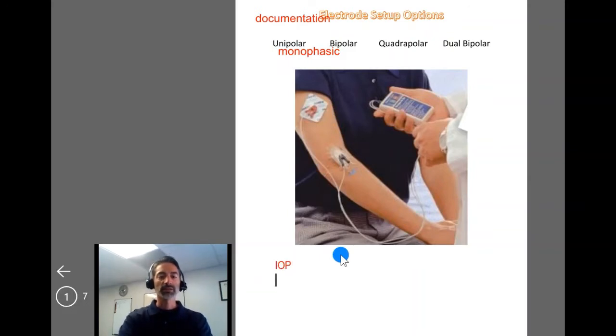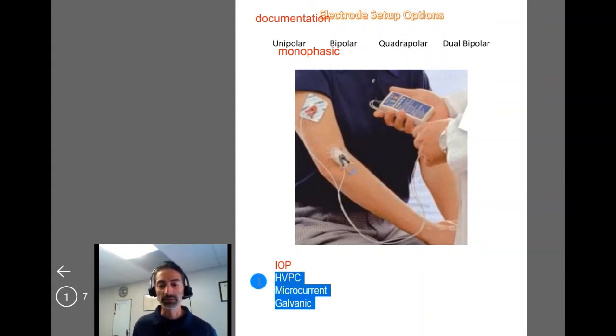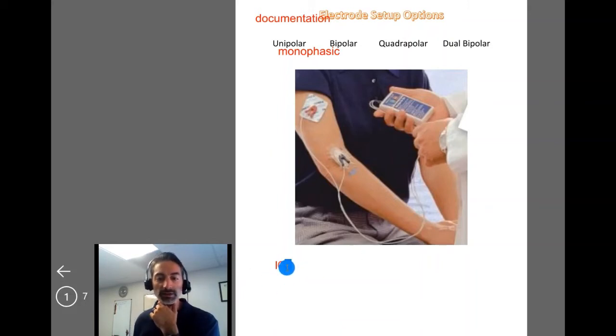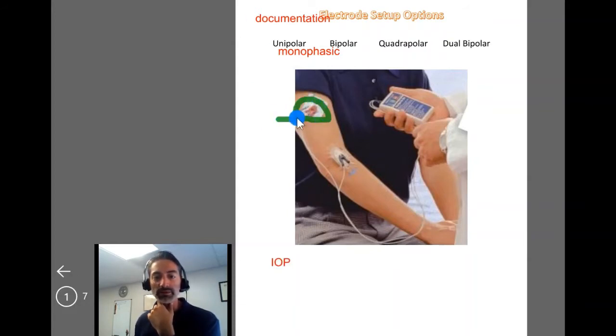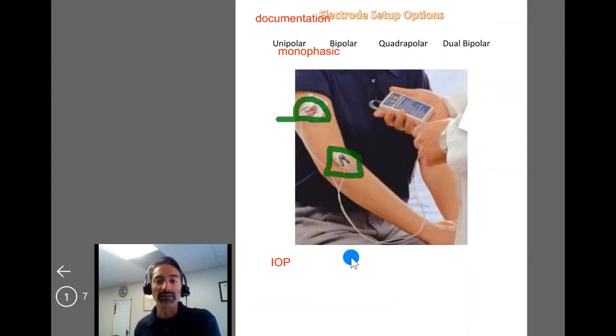Examples of a unipolar setup include iontophoresis, high volt pulsed current, and in some regards microcurrent. Galvanic with a continuous phase of direct current also qualifies. The one I would most highlight is iontophoresis — traditionally associated with a unipolar, monophasic setup. In these cases, it does matter which electrode is red for positive and which is black for negative, because that must match the medication underneath the electrode to repel the medicine into the tissue.